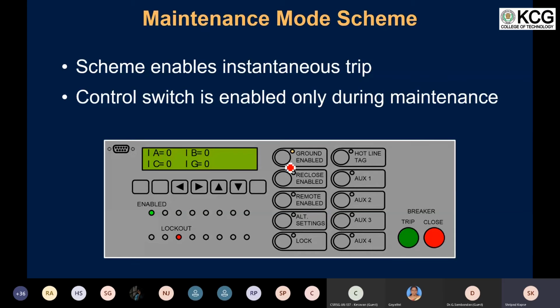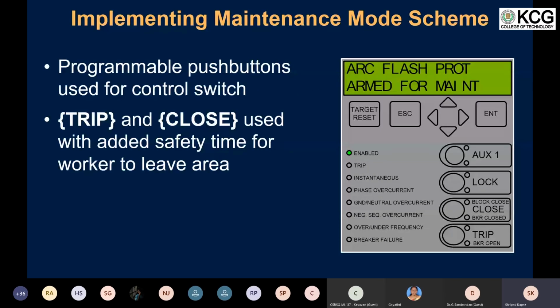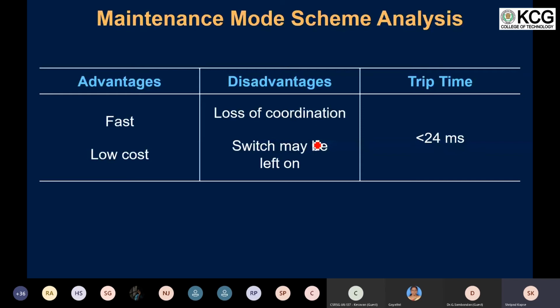And if there is a fault that occurs on the switchboard while the person is working on the switchboard, the relay would instantaneously trip. But there are some disadvantages related to that. That is, basically we are losing the time coordination. So if we are losing the time coordination system, that also basically means that we are losing the selectivity to trip whenever the fault occurs. So there are chances that in this case, even for an outgoing fault, your entire switchboard, including the incomer, may trip, and that is not expected in a power plant or in an industry.